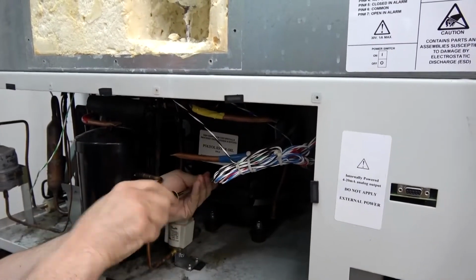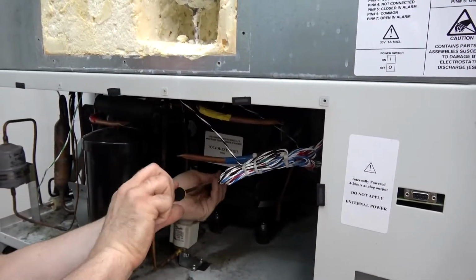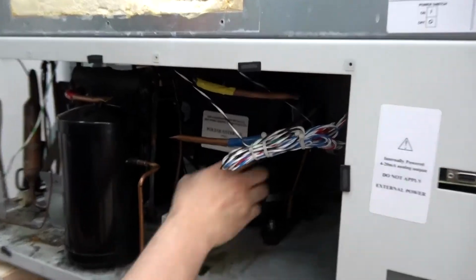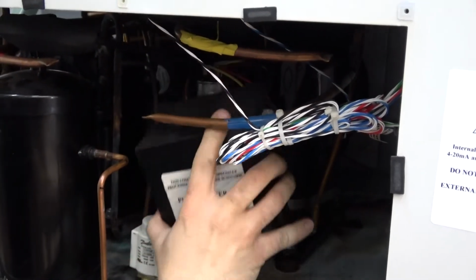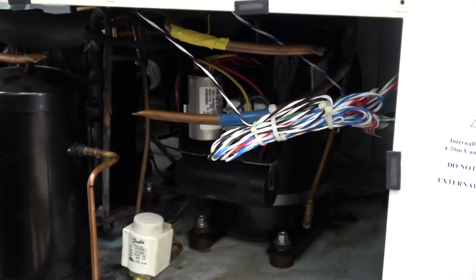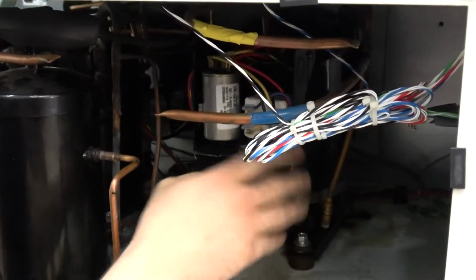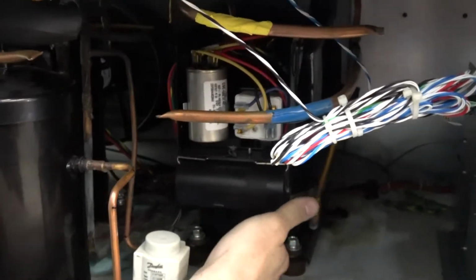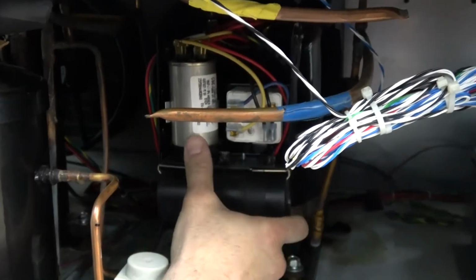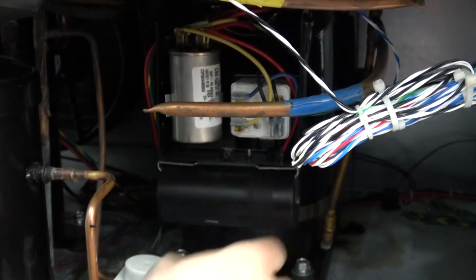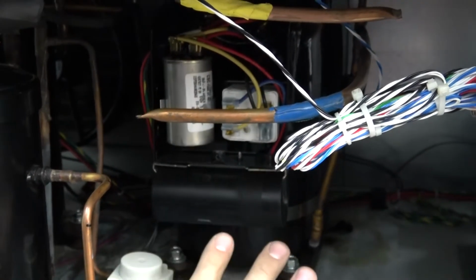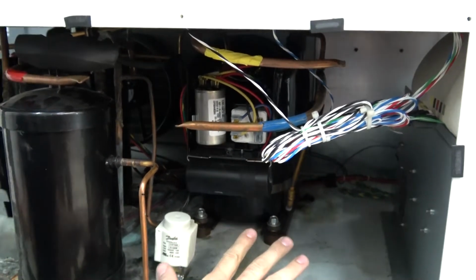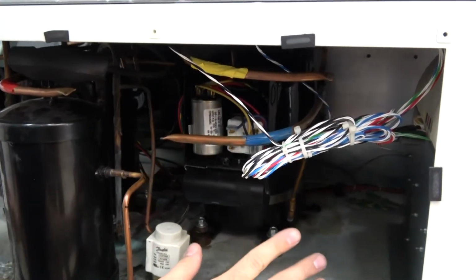It's not overly important, but it's something nice to know, because some of you may have experienced compressor failures, and sometimes it's just the capacitors. These compressors usually have two capacitors - a start and a run capacitor - that have to be on these units to make the motors function correctly. And sometimes they go out.